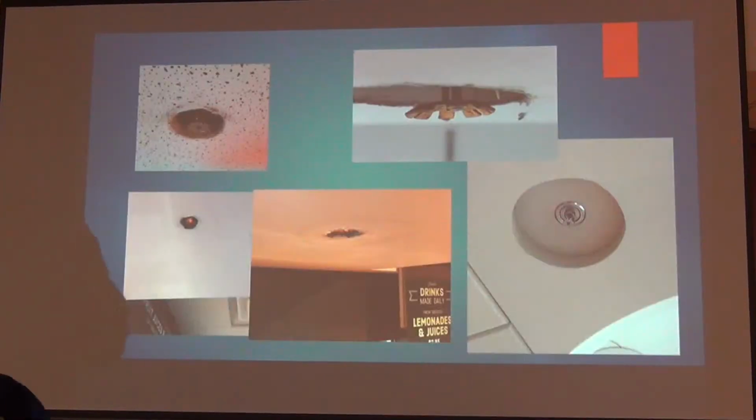Okay, obstructions. We talked about deflectors. This is the actual deflector that's an 1/8 inch clearance from the deck. You see how the deflector is bent down? That's the only way I can tell that, unless I look up the data, which I would always ask for. That is unacceptable, and so is that.